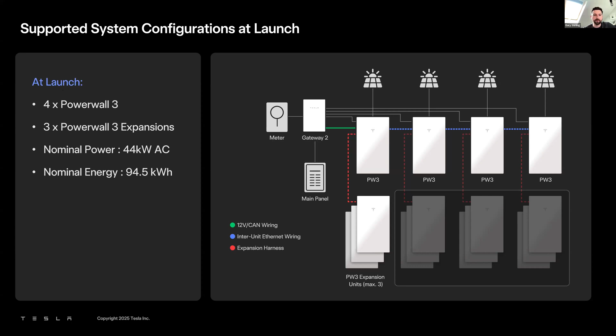This is just to give you a flavour of what you might need when it comes to expansion packs, because there's been a little bit of confusion. If you are stacking a Powerwall with an expansion pack, you need the Powerwall 3 expansion pack stacking kit, which is basically a new wall bracket and a plastic shim that goes between the 2 units. You will also need a DC harness - if you're stacking front to back, the 0.5 meter length is exactly what you need. If you're stacking them side by side on a wall, you need to order the wall mounting expansion pack kit.